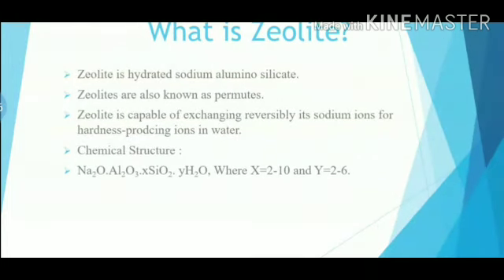Now, what is zeolite? Zeolite is hydrated sodium alumino silicate. They are also known as permutites. That's why this process is also called the permutite process. Zeolites are capable of exchanging reversibly its sodium ions for hardness-producing ions in water. Its chemical structure is Na₂O·Al₂O₃·xSiO₂·yH₂O, where X varies from 2 to 10 and Y varies from 2 to 6.